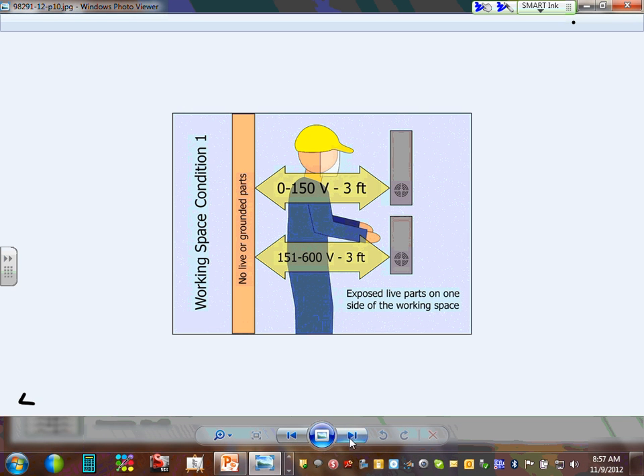Okay. All right. The second thing I'm going to highlight, guys, about panels is working space. When you work in the front of panels, you have to work safely and egress safely. For the working space of a panel, the code requires a depth of working space equivalent to the following. If your voltage is, this is phase to ground, if your voltage to ground is between 0 and 150, you have to have 3 feet of clearance in front of it, right? That's the minimum, for condition 1.